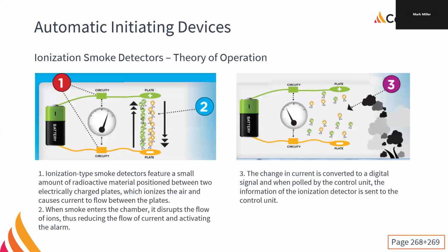Right. So ionization smoke detectors, right? We have electricity. We have a very small amount of radioactive material positioned between two electrically charged plates, which ionizes the air and causes the current to flow between the plates through the air gap. When smoke enters the chamber, it disrupts that flow of ions, so it reduces the current flow, and that reduction of current flow activates the alarm. And it works quite well.